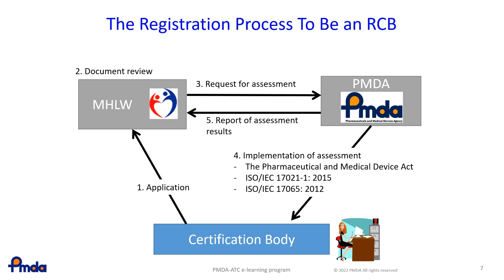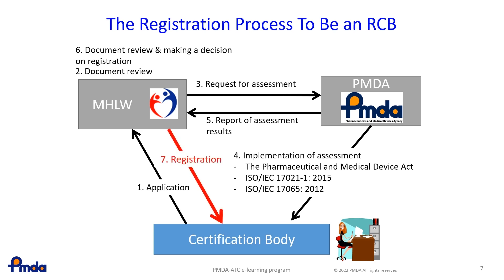After completion of the assessment, the PMDA reports the assessment results to MHLW. After receiving the assessment report from the PMDA, MHLW reviews the documents again and determines whether to register the certification body or not. If satisfactory, MHLW registers the certification body as an RCB.